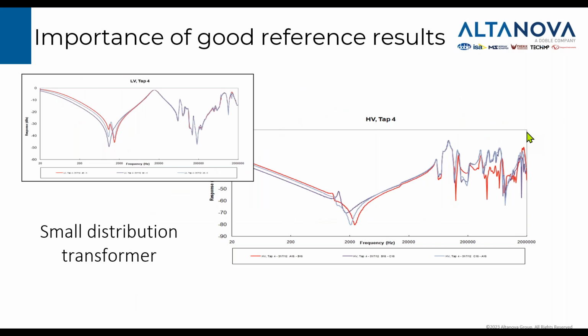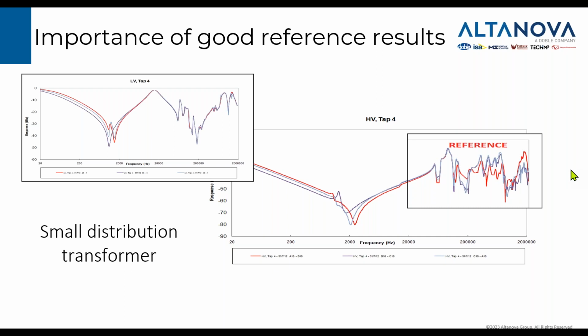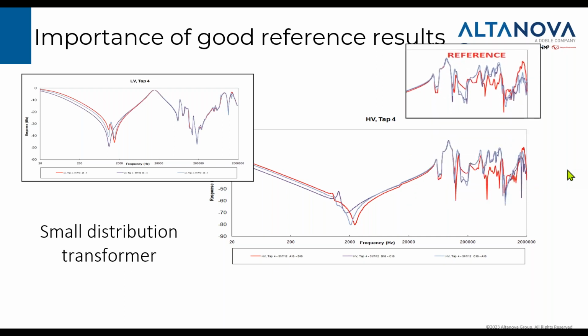Another transformer, another situation like that. Here we had a small distribution transformer with very good responses on the low voltage side, but with some relatively high differences of only one trace on the high voltage side. And again, we had a possibility to measure the sister transformer that was standing next to it. This time it was scheduled for testing, so we tested it. And this was the reference. So after measuring the reference transformer, we understood again that this is a genuine feature of this particular design.